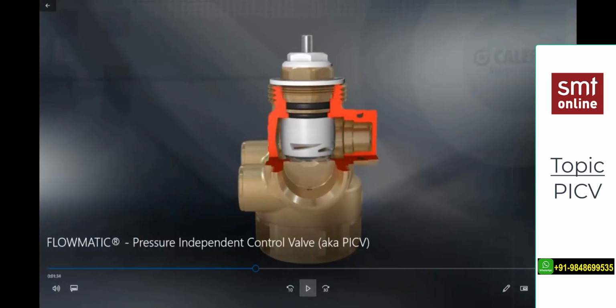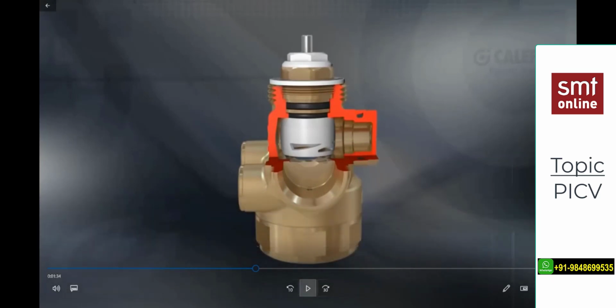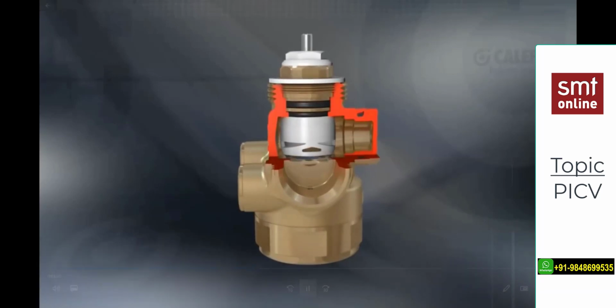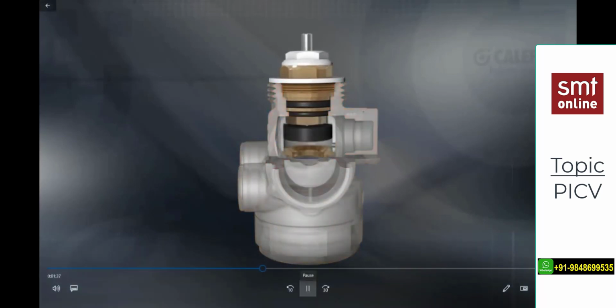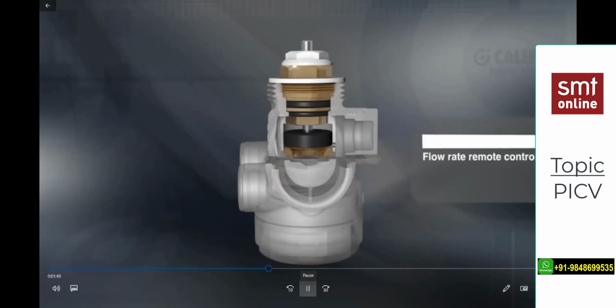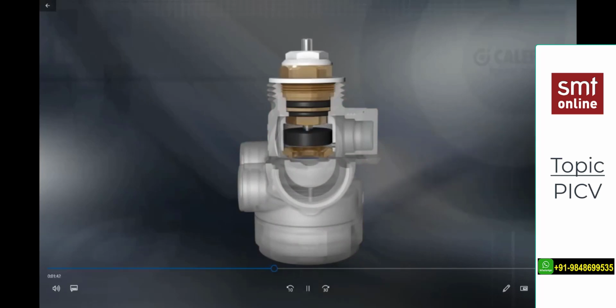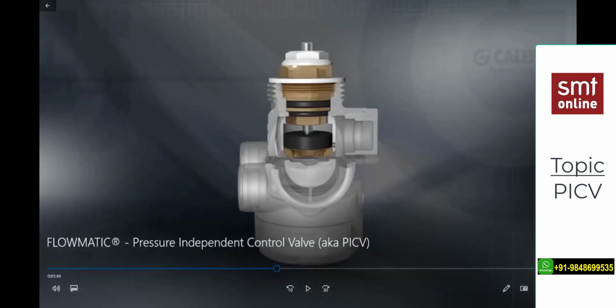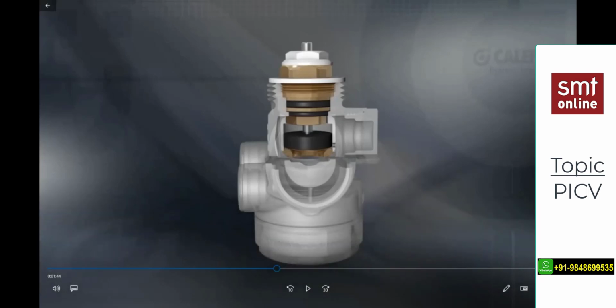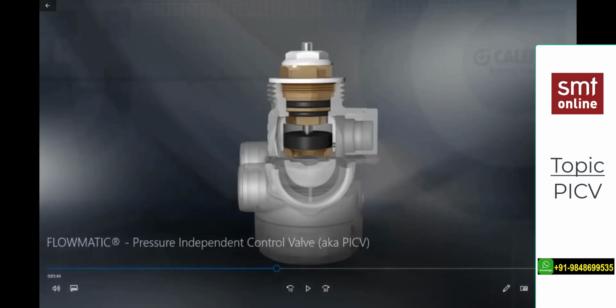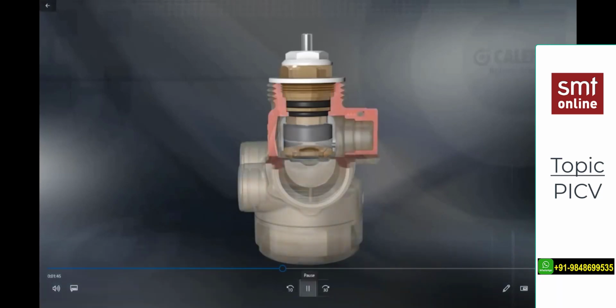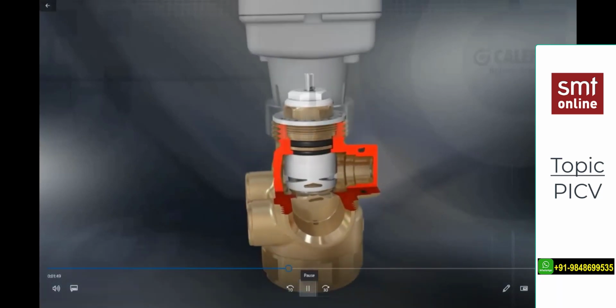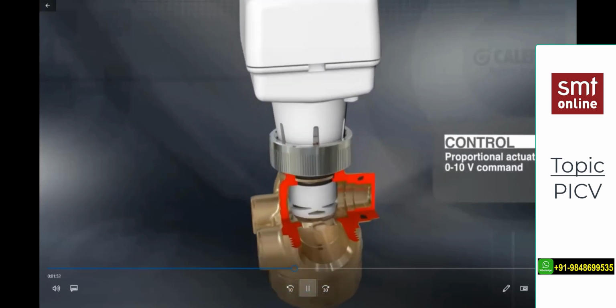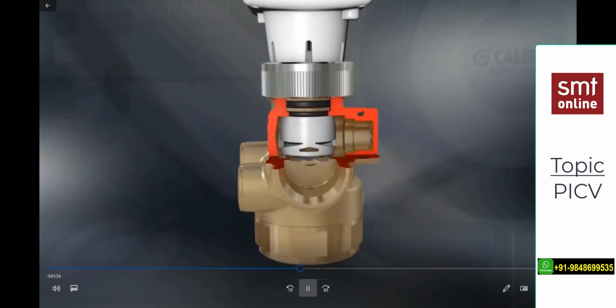It means with the PICV we can do the balancing, right? It works as a balancing valve, meaning a regulating valve, RV. Next, the second function: you see this is acting as a two-way modulating valve. This valve automatically goes up and down, connected to the actuator, as per the room temperature requirement, like a two-way actuator. This is the second function. It means it can also be used as a two-way modulating valve. So balancing and two-way, both in one.